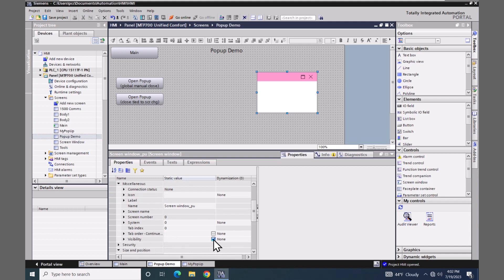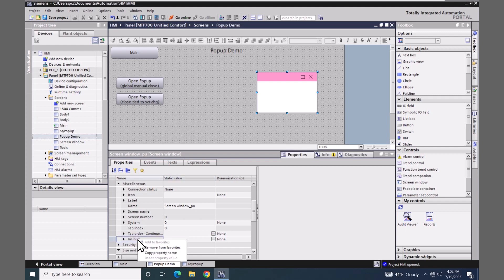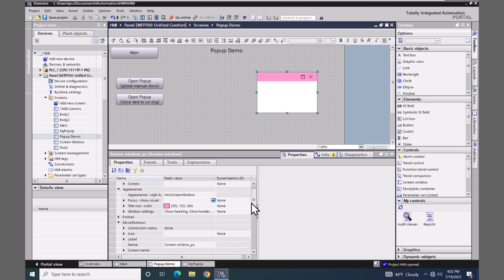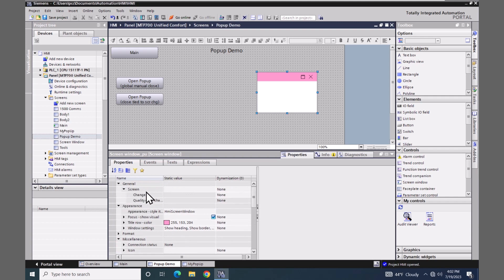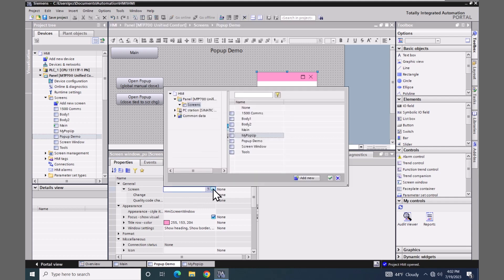Right now this screen window will be displayed when the screen is displayed. I'm going to uncheck this, and then you can dynamically control the visibility property through dynamizations or by changing the property values directly. I'm going to right-click on the visibility property and select copy property name — sometimes the names you see here may be a little different when you use an actual function call. I'll scroll up to the screen area and select the 'My Pop-up' screen to be displayed within this screen window.